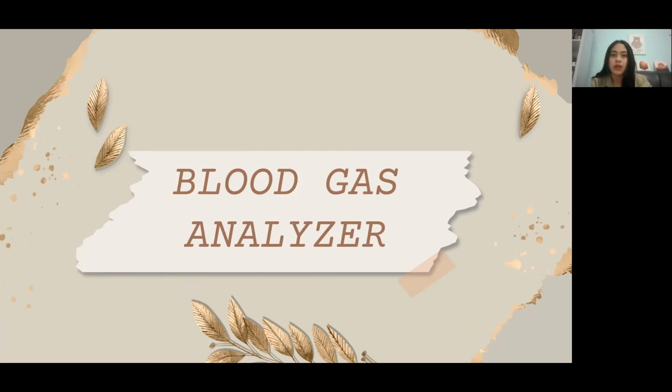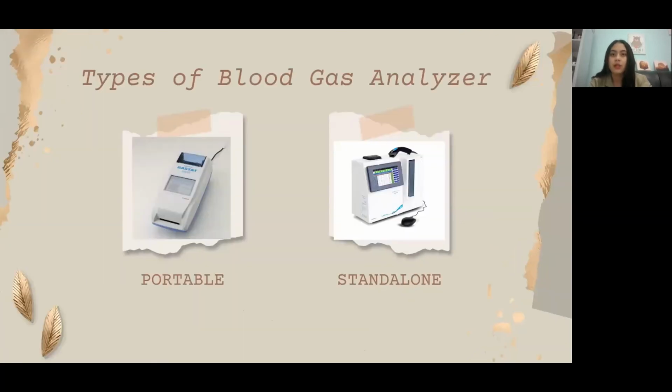There are two major types of blood gas analyzer, standalone blood gas analyzer and portable blood gas analyzer. The standalone blood gas analyzer has reagent pipes that provide reagent to measure the arterial blood gas value and a sensor cassette that packs all electrodes to measure different parameters. The portable or handheld analyzer consists of simple cassettes which determine the arterial blood gas value directly.